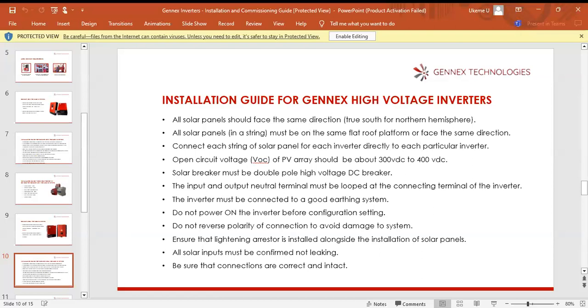Connect each string of solar panels directly to each particular inverter. This is applicable to all high voltage inverters. You don't connect solar panels and then connect all of them to a bus bar and start sharing for each inverter. It's not acceptable, and it could damage the inverter. So please don't go near that. Open circuit voltage VOC of the PV array should be about 300 volts DC to 400 volts DC.